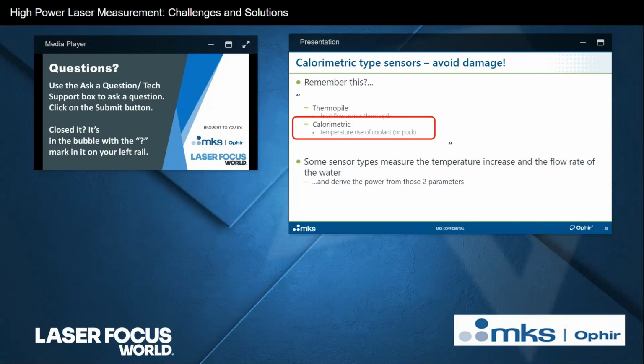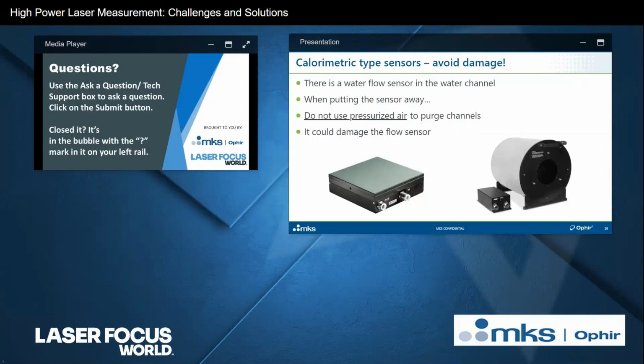Okay, you remember this? I mentioned calorimetric. So some sensor types are calorimetric rather than based on a regular radial thermopile. What happens there is that instead of measuring the heat flow radially outward from the point of absorption past the thermopile, the calorimetric sensor measures the temperature increase of the water, which obviously is a function of the power of the beam coming in, and it measures the flow rate of the water. Those two pieces of information combined enable the sensor to then derive the power that was coming in. So here you see some examples of calorimetric type Ophir sensors.